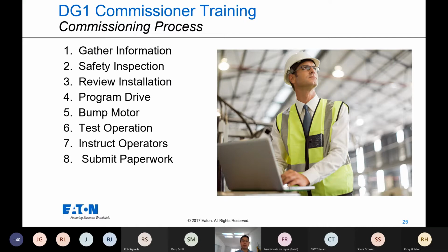The most important thing I would say, obviously other than the safety inspection and lockout tagout procedures, is to review your installation. So have your pump submittal, have your VFD submittal, maybe your control sequence of operation. Program your drive based off the motor nameplate. This is critical. Whatever values from your motor nameplate you program onto the VFD are going to be the basis on which all the safeties and algorithms are calculated onto the drive.